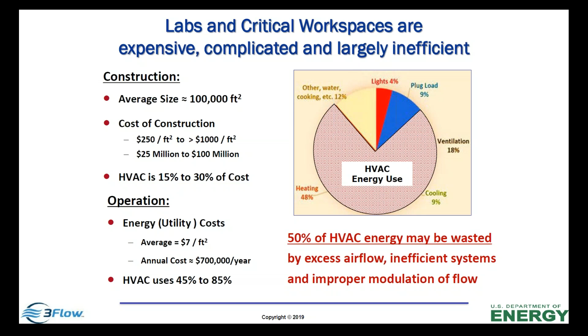And what we have found from all this data, with the 40,000 plus hoods that we've tested, is about 50% of the HVAC energy is wasted by excess airflow, inefficient systems, and improper modulation of flow. That has to do with a building that is brand new, that just comes into service, and also a building that's been operational for years, but without paying attention to some kind of a process or plan to maintain that building. These are the kinds of energy that's wasted in a lab building. Next slide, please.